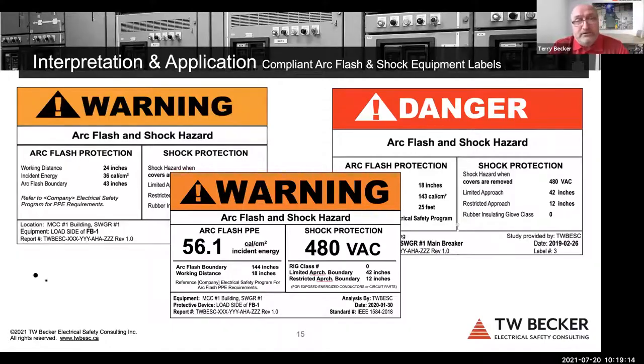So again, there are literally hundreds of thousands, if not millions, of labels installed across North America. And from my review of these labels with clients, I'd say 50 to 75% of them are not compliant labels and do not provide the right information to the qualified electrical worker or the task qualified worker. The bottom of that label is where there's also a gap. The information on the bottom of the label should be clear with respect to where the incident energy applies, and related to the electrical protective device that the incident energy was calculated based on: load, line side, bus of that protective device. And I find on a lot of labels that is not clear.